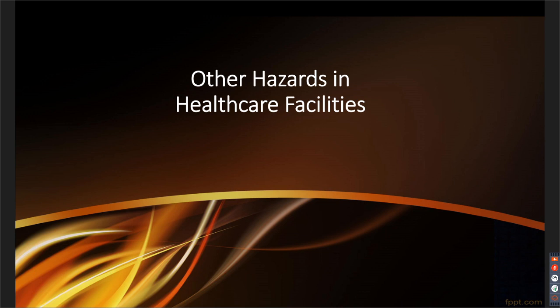So fire resistance rated glazing and fire protection rated glazing are two different things. Yeah, it all looks like glass, but the difference is in what test that glazing has to go through. If you think of the words fire resistance rated, like your fire resistance rated assembly, that assembly is like your wall, your fire barrier, your fire partition. Those are required to go through tests that meet the standards in ASTM E119, UL 263. Similarly, fire resistance rated glazing would have to go through those same tests, so it's tested as a wall, as opposed to the fire protection rating, which would go through a different test. So it's how that glazing is tested. Is it tested as a wall, or is it tested as the opening? And you would find that, of course, with the product data and the test reports that come with that material.